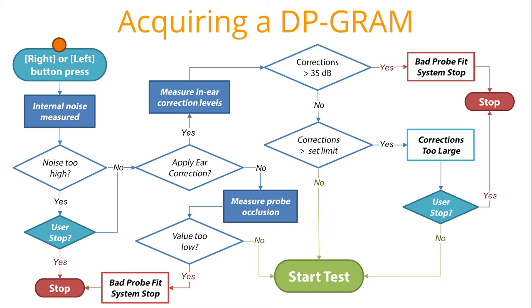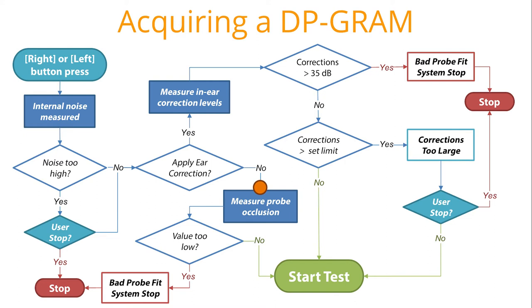After probe insertion, select right or left ear to initiate the test. The internal noise measurement is taken and compared to a noise template. If the noise is too high, you will get a noise-too-high warning message and will be asked to stop or proceed. If you stop, we suggest: one, ensure you are in a low noise testing environment; two, instruct the patient to be as quiet and still as possible; and three, pick a larger ear tip that seals the ear canal better and refit the probe with a deeper insertion. Next, the program evaluates if the ear correction in-ear calibration option is turned on. If not active, the software proceeds to look for probe occlusion using the first test frequency pairs. If the measured value is 35 dB below the desired level, you will see a probe fit error message and the test will be stopped.